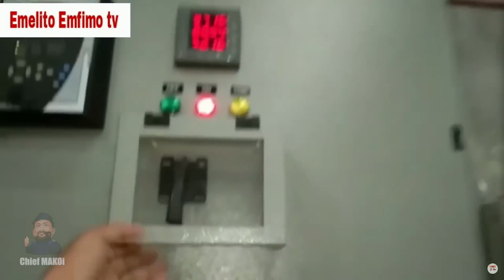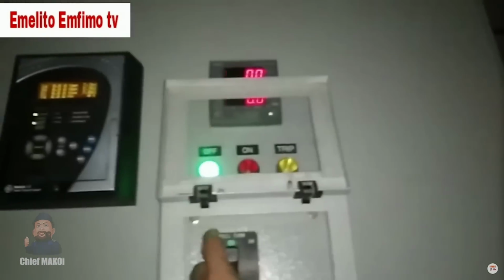Which led to the question that was raised in the comment section by a lot of viewers. Isn't it safer to keep the bus tie open and use two transformers while the ship is maneuvering into or out of port? This way, in case one transformer fails, a blackout won't occur. Well, the quick answer is yes, it will definitely be safer if that will be done. However, a lot of cargo ships are not designed to easily do that. On some ships, bus ties are not even breakers that you can simply flip to open or close.